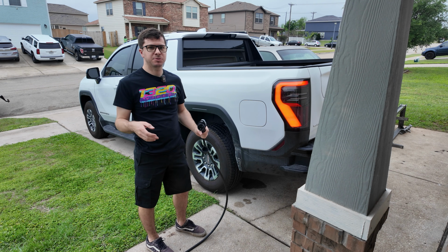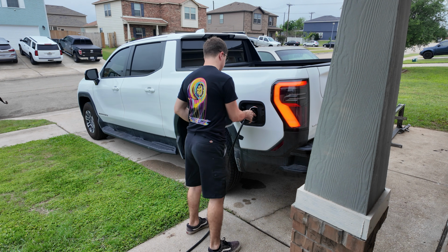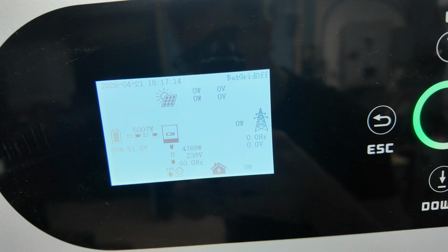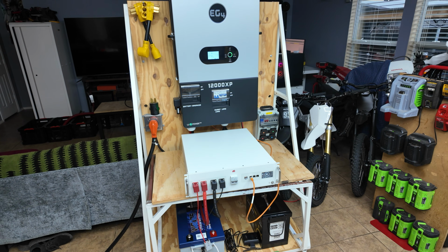We have the EV charger set to 20 amps, which would give us around 5 kilowatts. And there we go, we're right at 5,000 watts out of the battery. We're showing 5,100 watts, 100.7 amps. I'm just gonna let this thing run and see what happens.